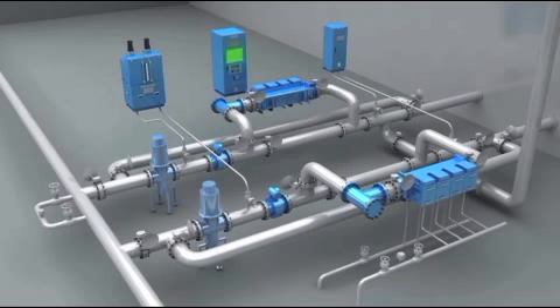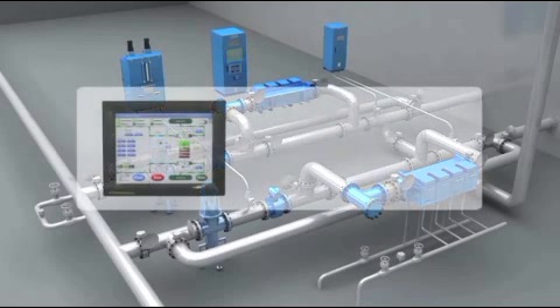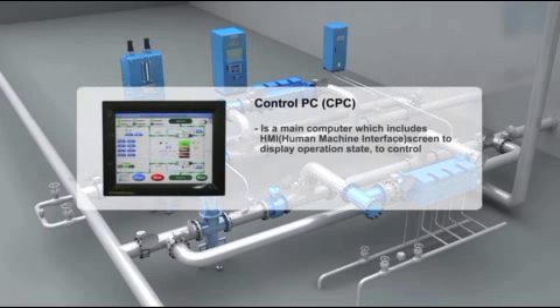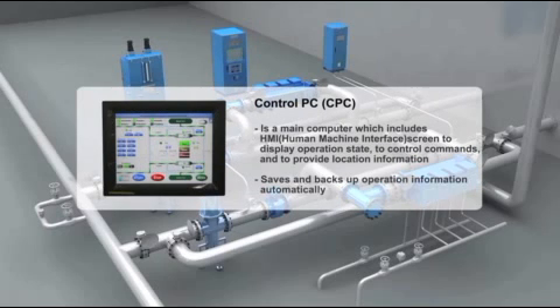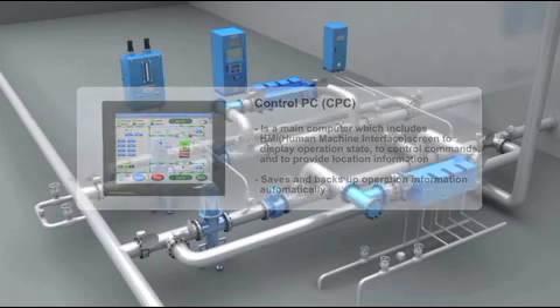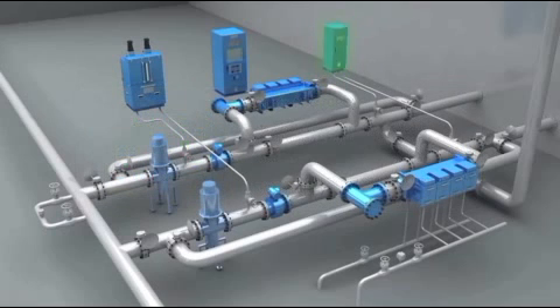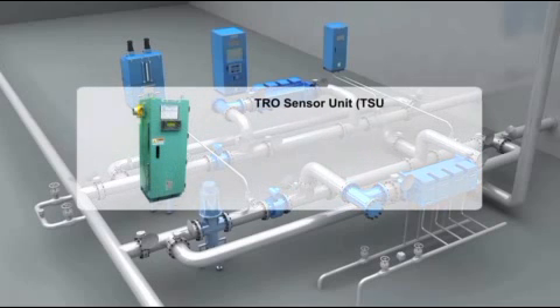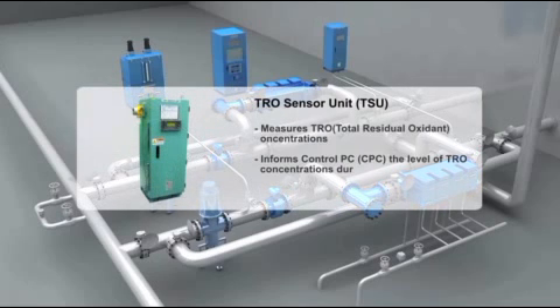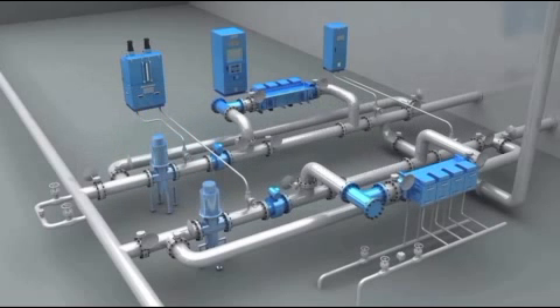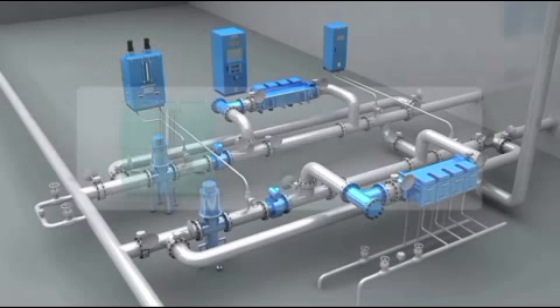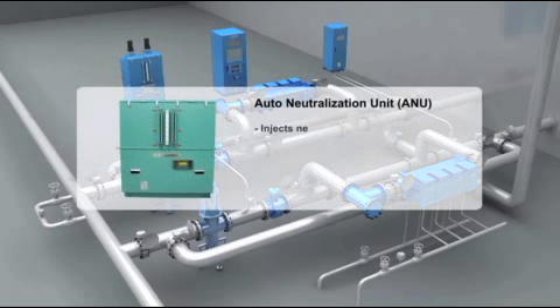It is a main computer which includes an HMI, human-machine interface, screen to display operation state, to control commands, and to provide location information. It saves and backs up operation information automatically. It measures TRO, total residual oxidant, concentrations, and informs the control PC, CPC, of the level of TRO concentrations during ballasting and deballasting operation. It injects neutralizing solution automatically to neutralize residual TRO prior to deballasting operation.